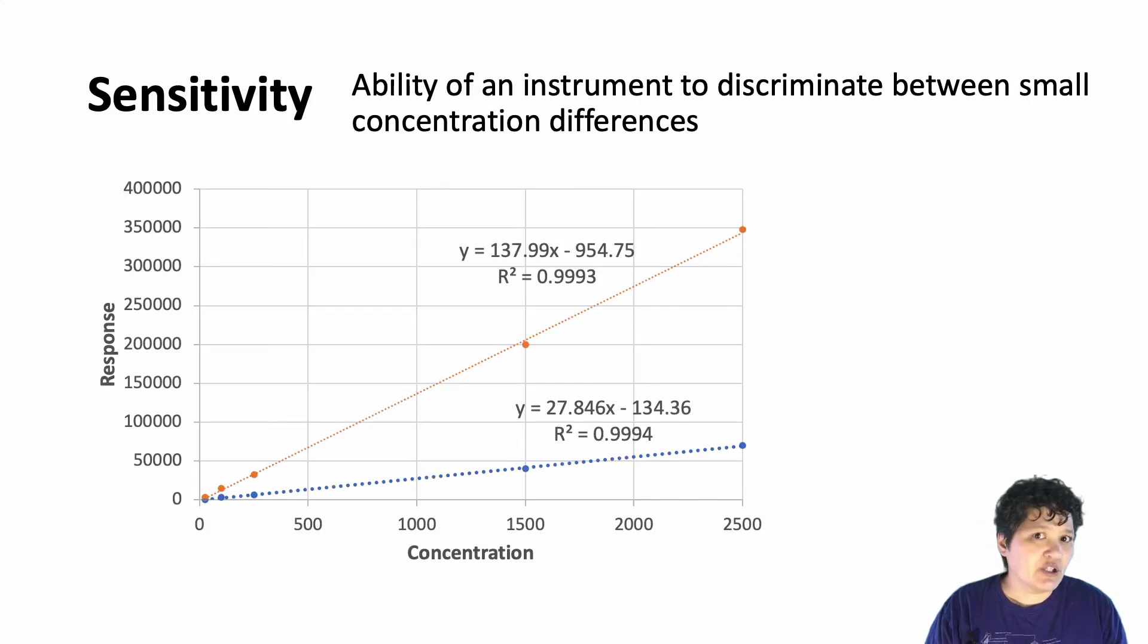One of the things we can determine from looking at a calibration curve is what we call the sensitivity of an instrument. In general, the sensitivity of an instrument is its ability to measure very small differences in concentrations. And the larger the slope of the calibration curve, the more sensitive your instrument is. For example, you can look at these two calibration curves, which were made using the same concentrations. And notice that the difference between trying to measure 88 ppm and 90 ppm would be much more difficult to measure using the blue calibration curve and much easier to measure with the red curve.